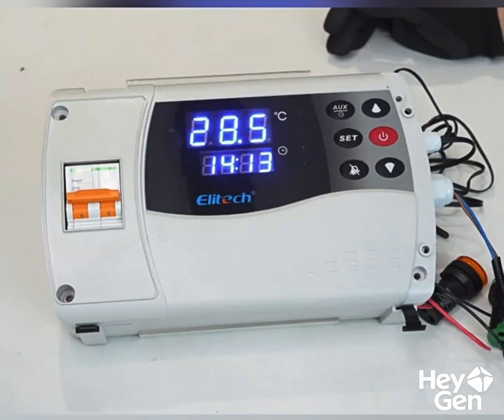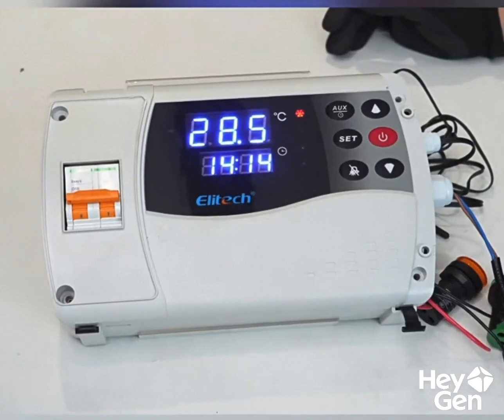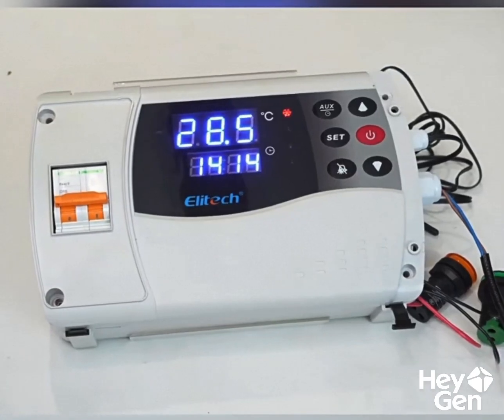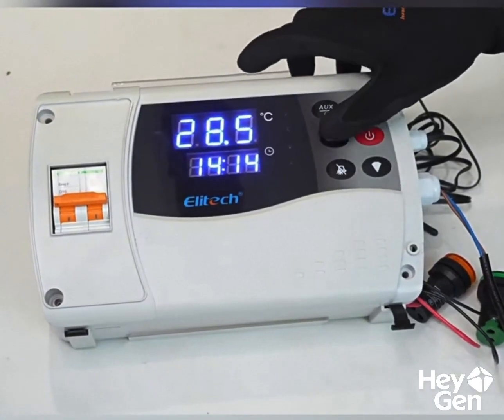If we want to set a temperature range for switching between cooling and heating, for example from 7 degrees Celsius to 13 degrees Celsius, we can set the control temperature to 10 degrees Celsius and the control hysteresis to 3 degrees Celsius. First, we press the Set button.